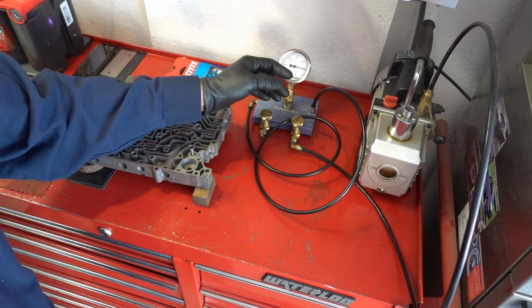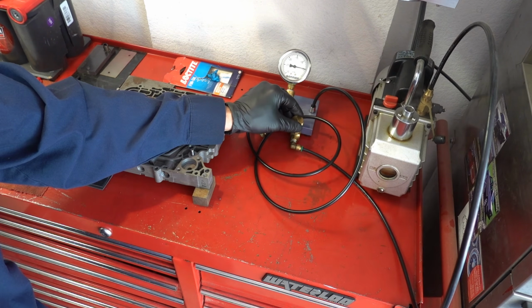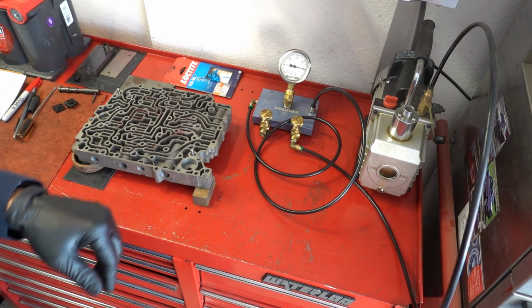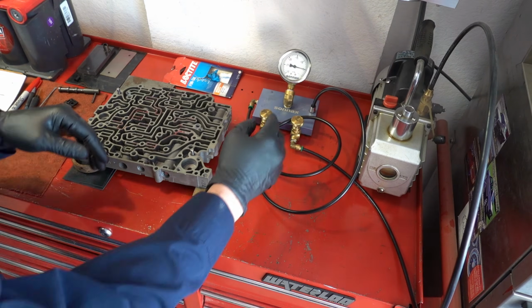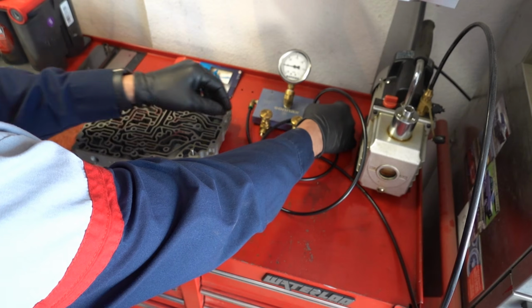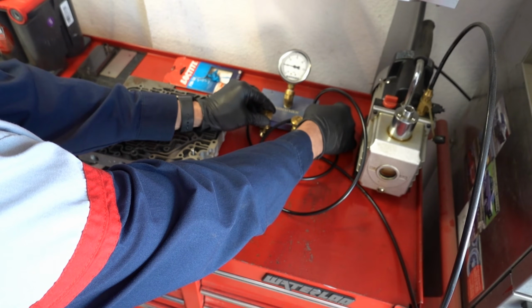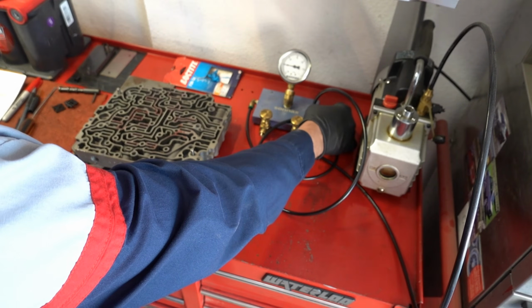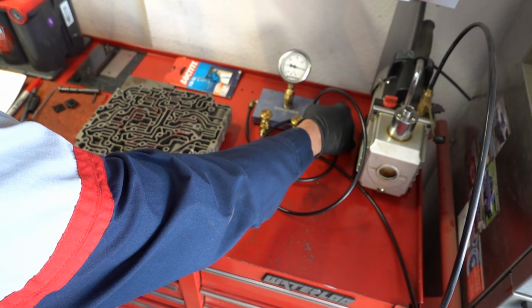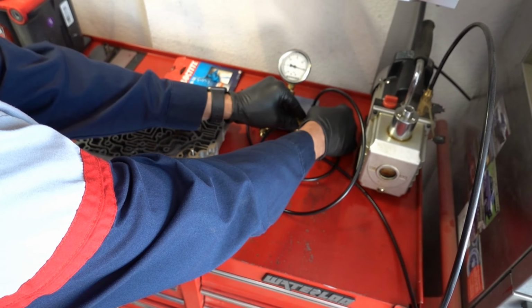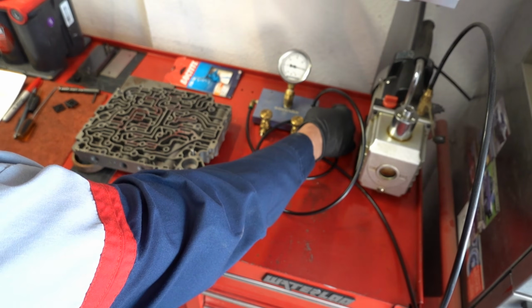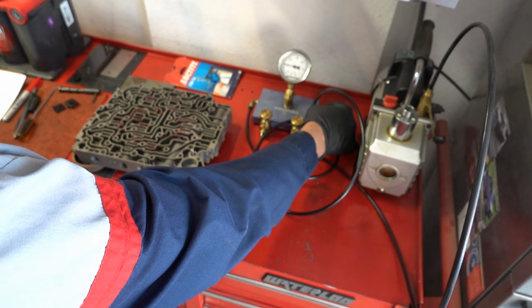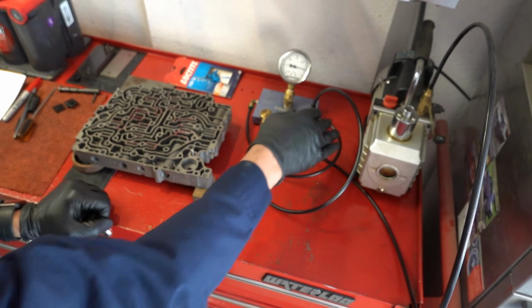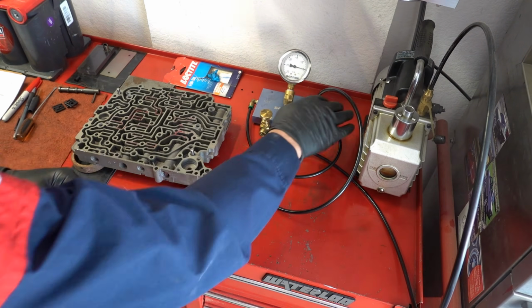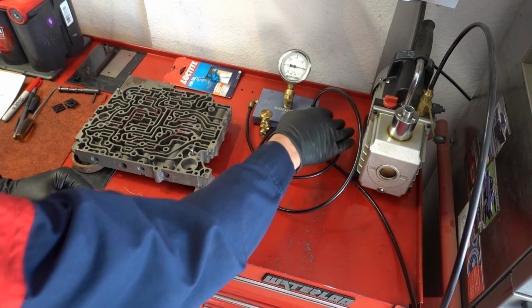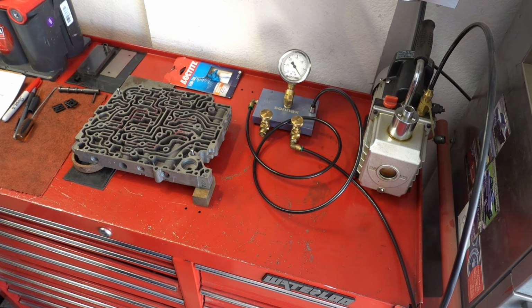So it looks like we have about 5.5 inches, maybe just shy of 5.5. So we're going to adjust the pump valve clockwise to lower that vacuum down to 5 inches. Okay, once it's reading a steady 5 inches, go ahead and use a finger to plug the calibration receptacle. We are a hair over 25 inches of vacuum, so adjust the bleeder valve counterclockwise to lower the vacuum until you get to 25, and then readjust as you need to your base calibrated vacuum once you remove your finger. So check it again, we're at 5. Now we're at 25. Back to 5. Do it a couple of times, make sure, and you're good to go. So now the machine's ready for use.